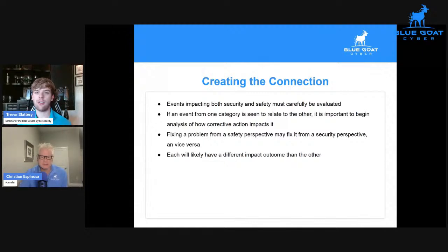If we're looking at the perspective through the FDA and in general the perspective that we should follow, the FDA's biggest concern is around patient safety and patient data loss. So if we have a very high severity security impact, but it's not necessarily going to harm the patient or not necessarily going to lead to patient's data getting disclosed, it's not as big of a deal as opposed to if we have a very high risk from a safety perspective. So in general, safety is going to be the bigger priority from the FDA. Both are very important, but if we have a high security risk and a high safety risk, usually the safety risk is going to take priority. Now, oftentimes there can be a single risk with different impacts on either, and so understanding which is the appropriate one to prioritize, usually going to be safety, is an important skill to have.